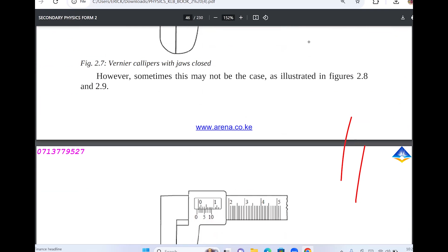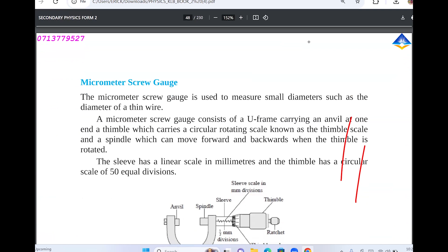Somebody will ask you to explain what zero error in a vernier calipers is. So the jaws closed, but no object in between. The zero mark on the vernier scale and on the main scale should coincide. The instrument is considered to have a zero error if the zero mark on the main scale is not coinciding with the zero mark on the vernier scale. I already talked about that. For the micrometer screw gauge, the zero mark on the thimble scale is not coinciding with the center line. Remember I talked about the center line last time?